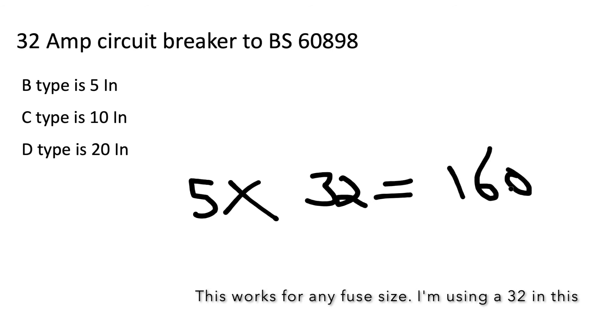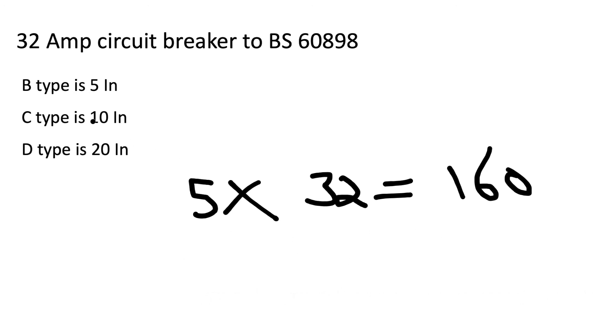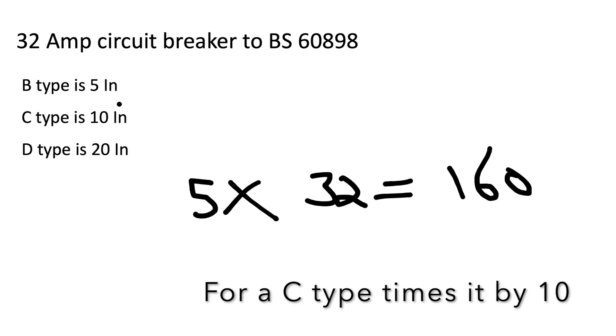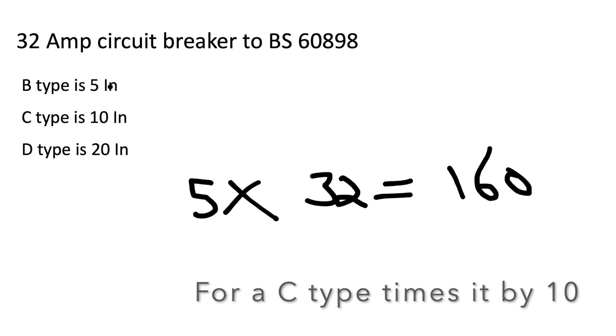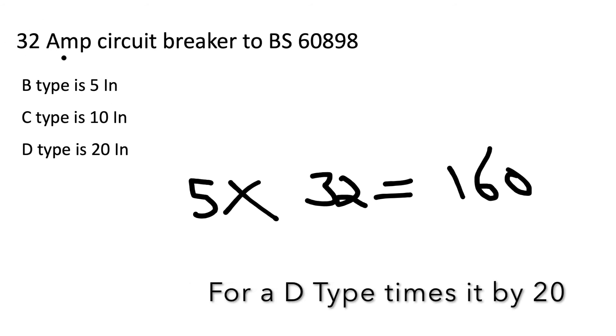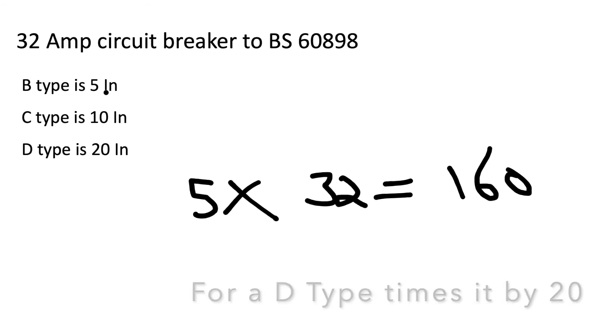We're going to use the 32 amp circuit breaker 60898. What I'm writing on the screen here is 5 times 32 - if you see under B type it says 5 IN, and all that means is you times it by 5 the size of the fuse and it gives you 160. 160 is the amount of amps required to blow that 32 amp fuse in the required time between 0.1 and 5 seconds, so it would comply. We can use that now in the next part of the formula.